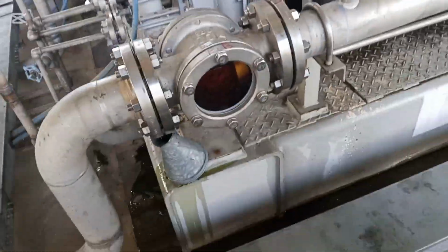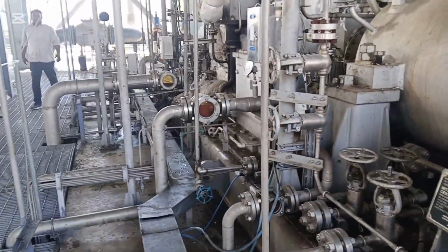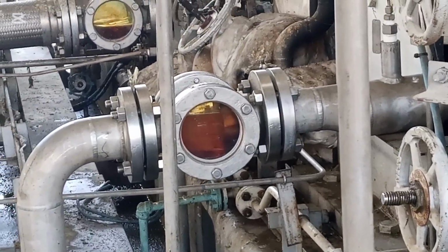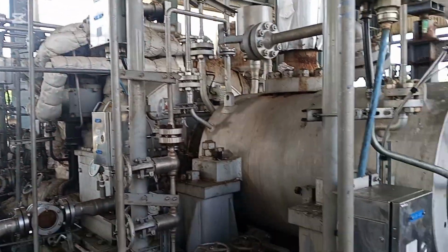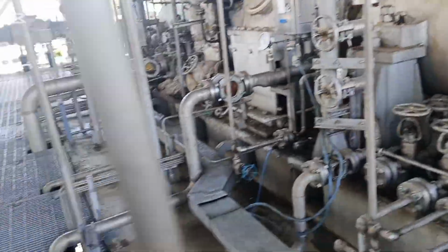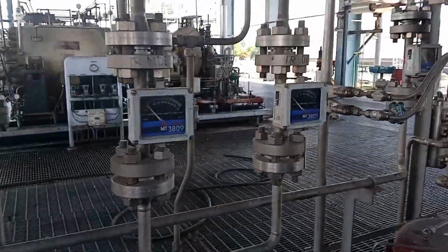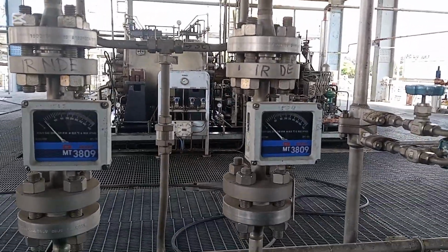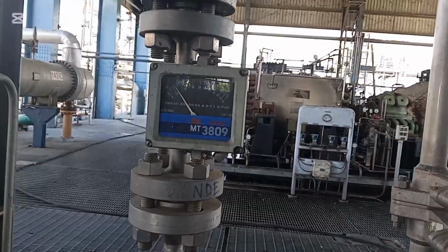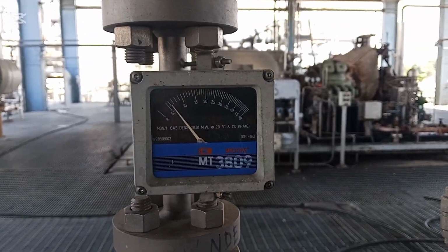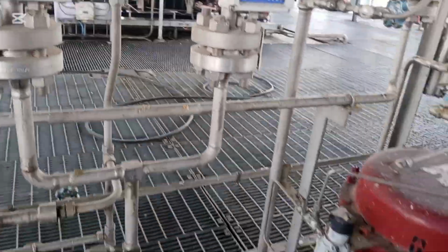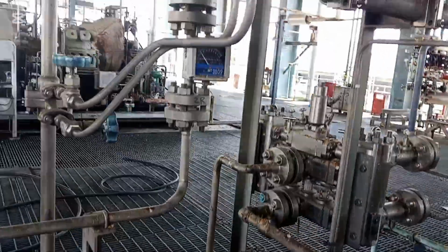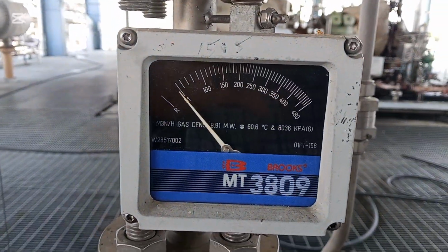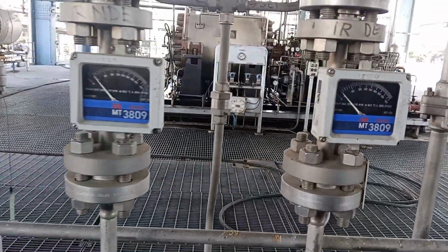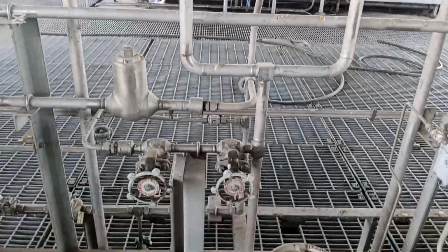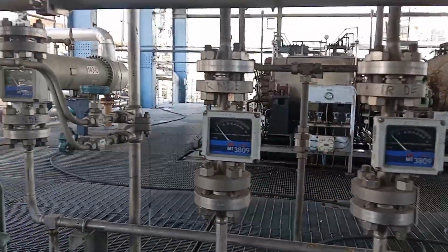After changing, all the parameters are okay, and nitrogen flow is okay, oil flow is okay, its temperature and vibration are okay. This is the nitrogen flow meter, and here the reading is within the range, and there is a control valve which controls the nitrogen flow. This is the control valve, and here is also the bypass valve and also the filter elements. We checked the filter, and after completing the maintenance work, also we changed the filter.